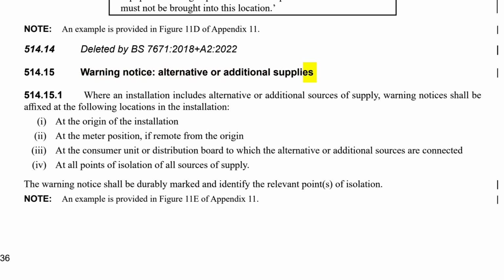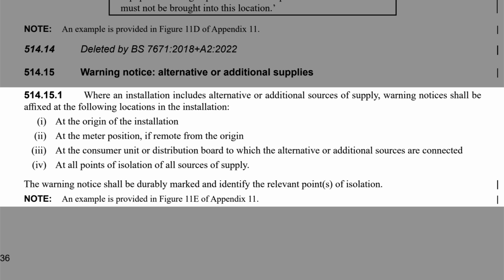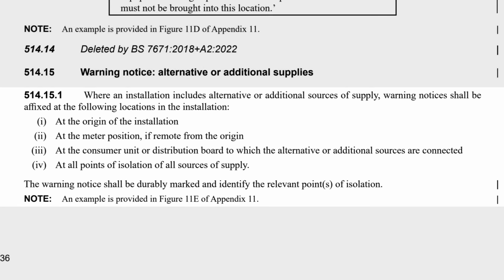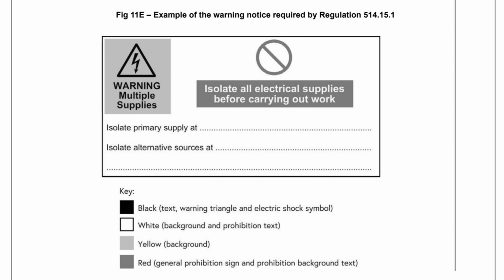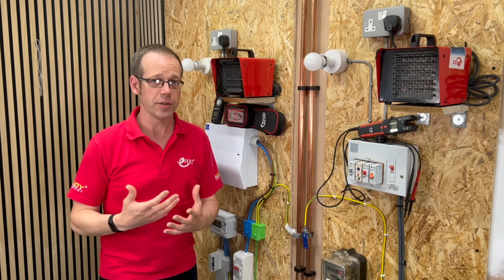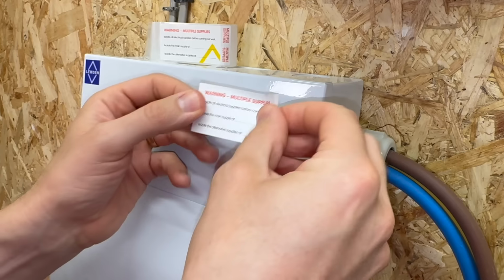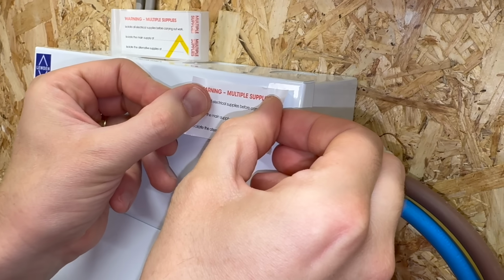Regulation 514.15.1 reads, where an installation includes alternative or additional sources of supply, warning notices shall be affixed at the following locations in the installation: at the origin of the installation, at the meter position if remote from the origin, at the consumer unit or distribution board to which the alternative or additional sources are connected, at all points of isolation of all sources of supply. The warning notice shall be durably marked and identify the relevant points of isolation. We're given an example of this in figure 11E of Appendix 11. Hopefully the electrician who went before us is every bit as diligent as we are and has installed bidirectional devices where necessary and stuck warning notices in all the relevant places.